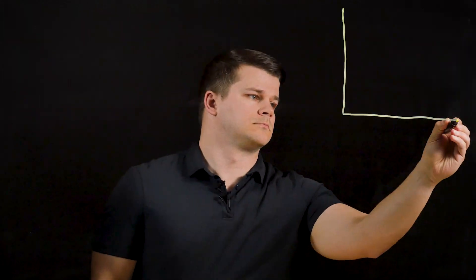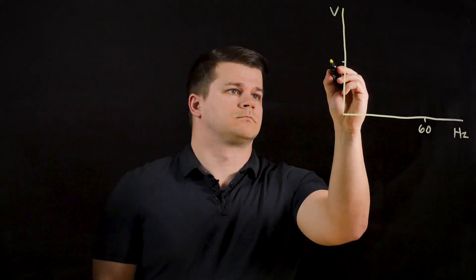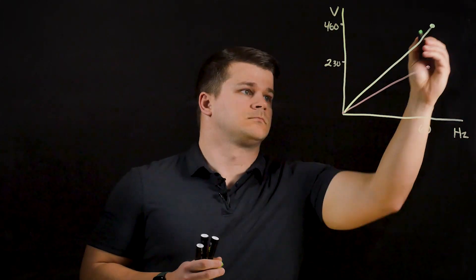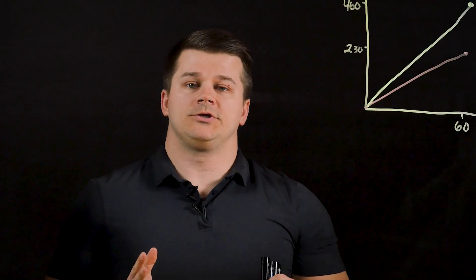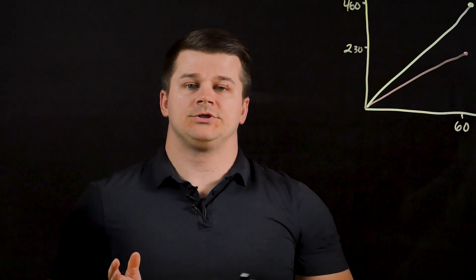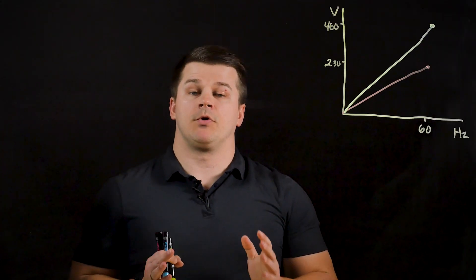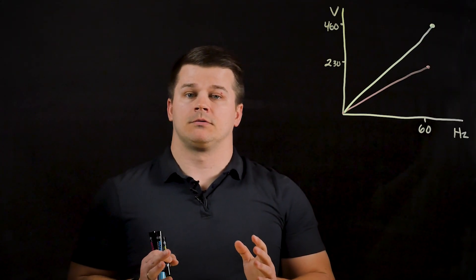In this video we're going to talk about the volts per Hertz control and how it can be used with a VFD to run a motor. Based on Faraday's law, if you keep the ratio between the voltage and frequency constant, you'll develop the motor's rated torque.